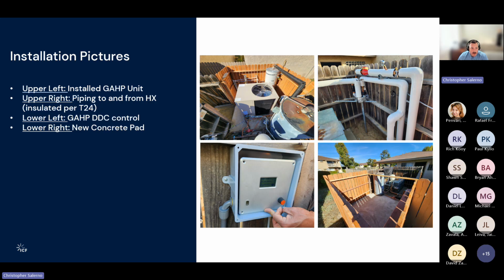So up here at the top left, I want to kind of go in order now. Sorry, I went out of order. This was the installed gas absorption heat pump itself. So you can see here, this beautiful unit right here. It's on the concrete foundation with the buffer tank behind it. I think this is an 80-gallon buffer tank. And so that was sized appropriately to provide enough water glycol mixture into this loop to provide enough heat transfer for this unit.